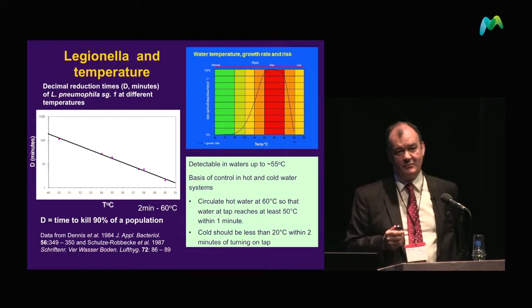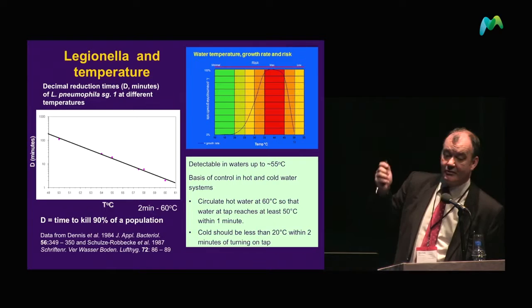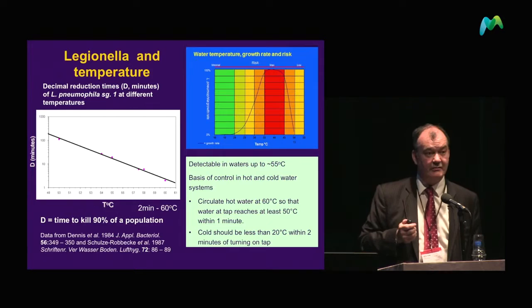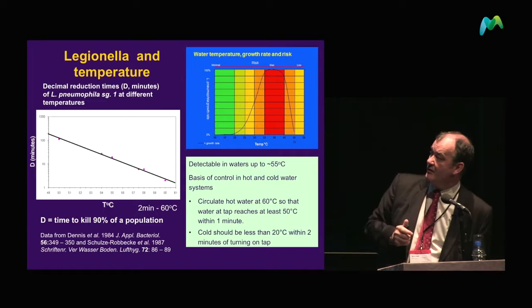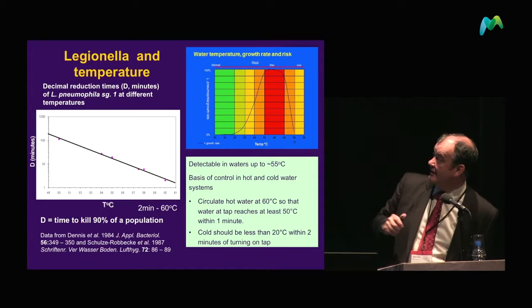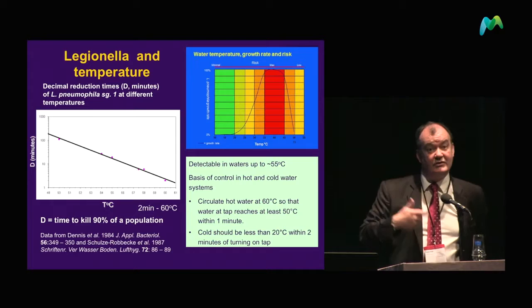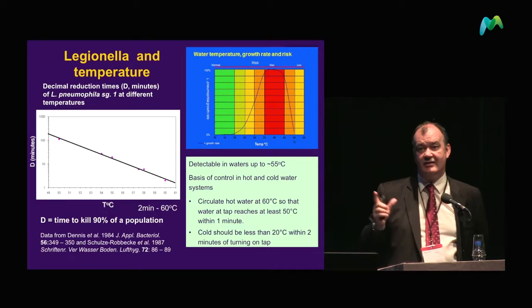Temperature is an important feature. This slide shows the optimum range within which Legionella will grow — 25 to 50 degrees — and on the other side, the time it takes to kill 90% of the Legionella population. Very few Legionella survive beyond two minutes at 60 degrees, which is one of the temperatures we set in terms of Legionella control.